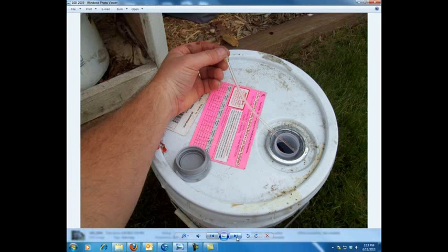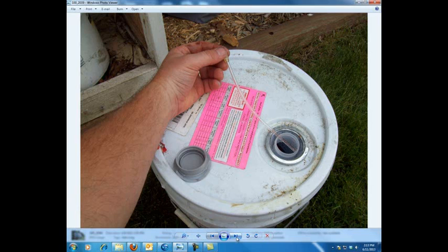I mixed my solution — this is a video I recorded after doing all the installs, which is why I had some extra heat transfer fluid glycol mix with water already stored in my bucket. I only had about half a gallon left. I took that sample, added it to the refractometer, put it on the slide, and followed the rules from a previous lesson.